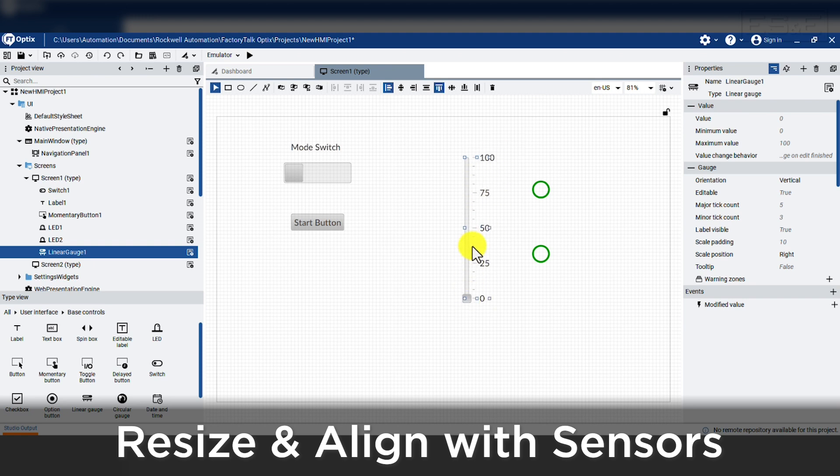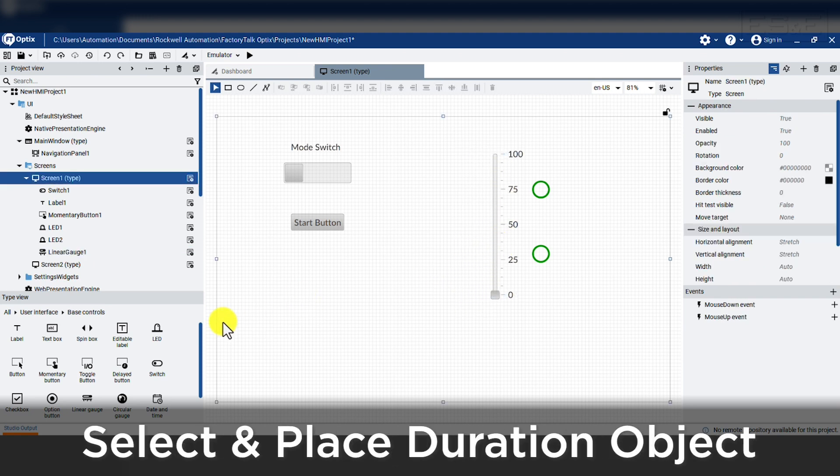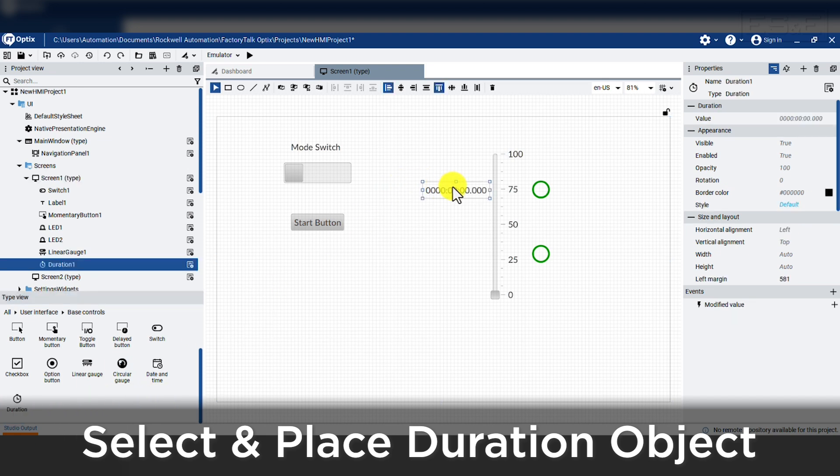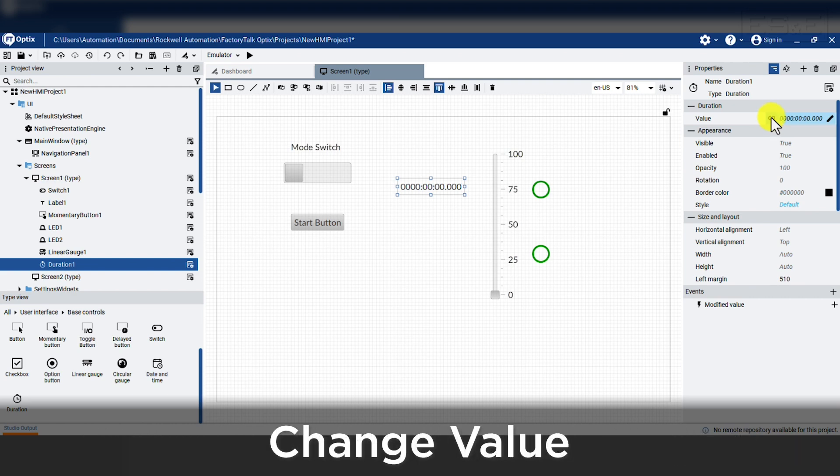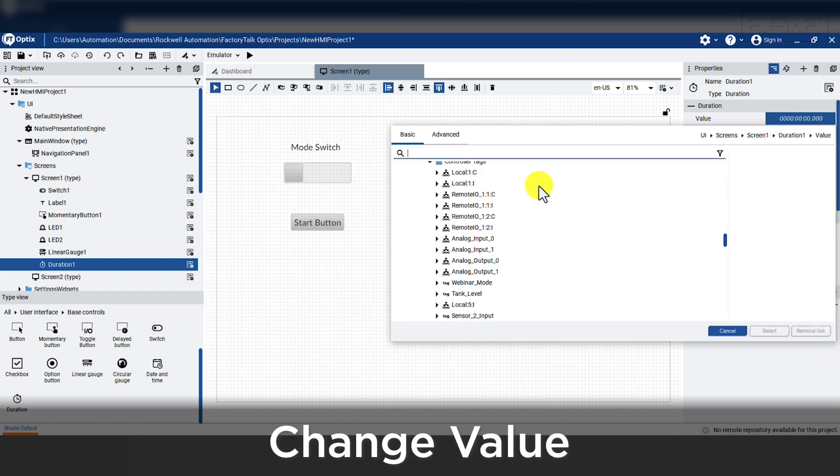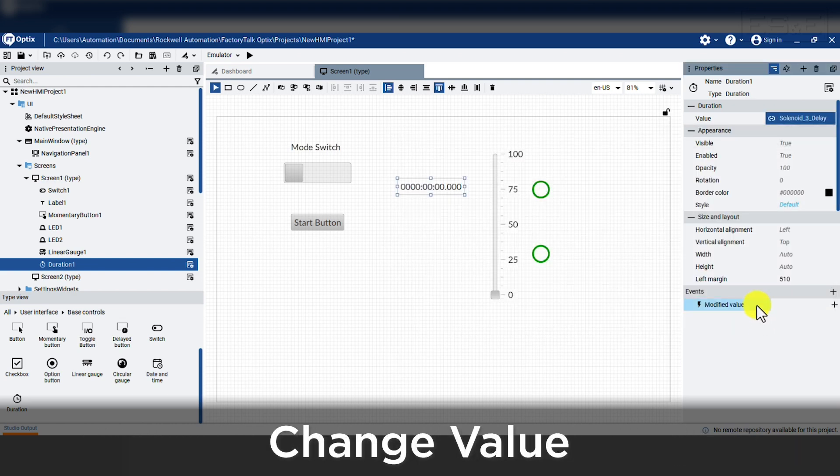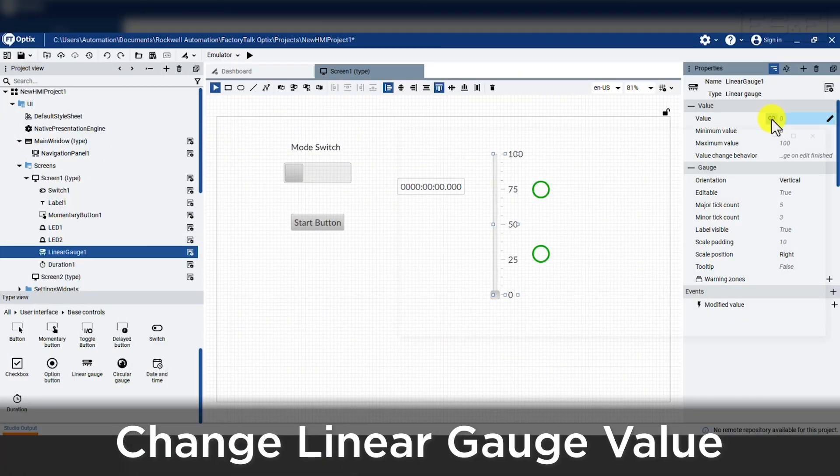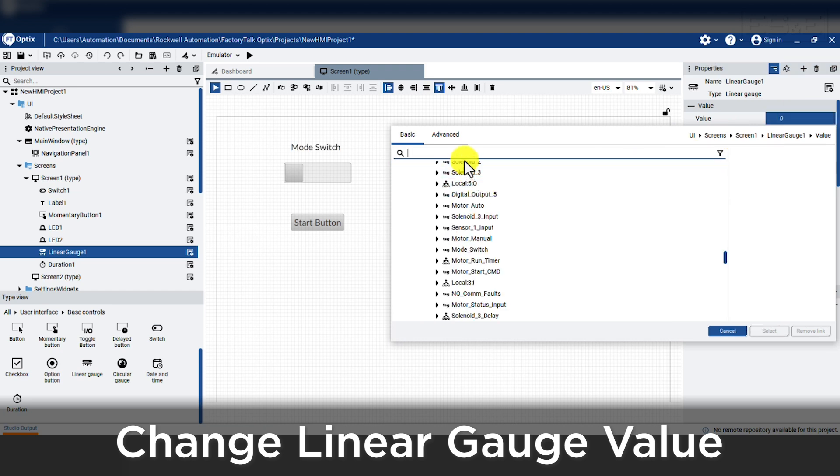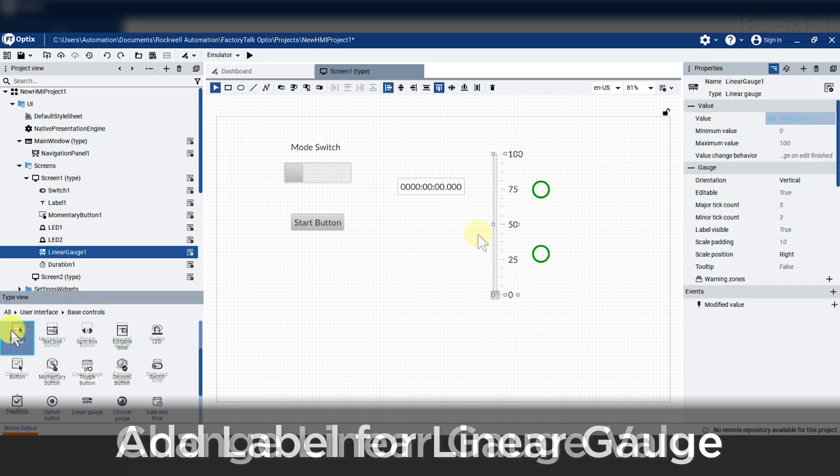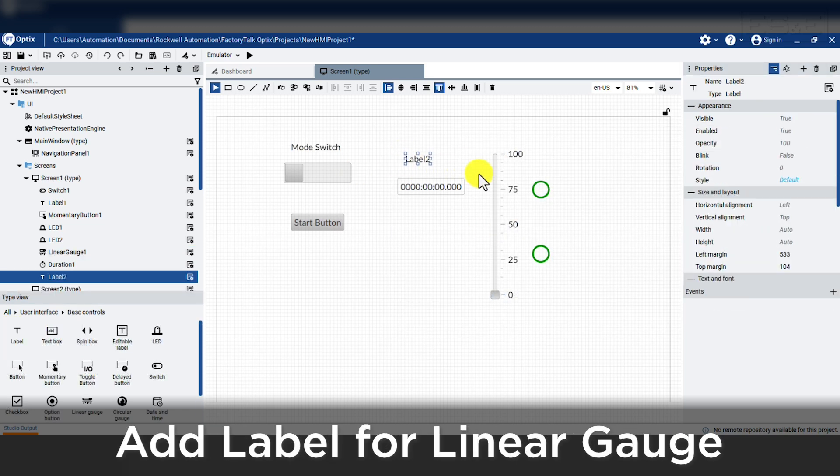Now we will add a duration object to allow us to modify a timer. Drop the object onto the screen and change the value of the tag to solenoid3 delay dot preset. That is all we need to do for this object and it works really well for timers because it has the ability to do unit conversion right in the object to get milliseconds into the controller. Last, we need to link a value for the gauge and we will add the tag called tank level. Now we will add a quick label to say solenoid3 delay above our numeric input.